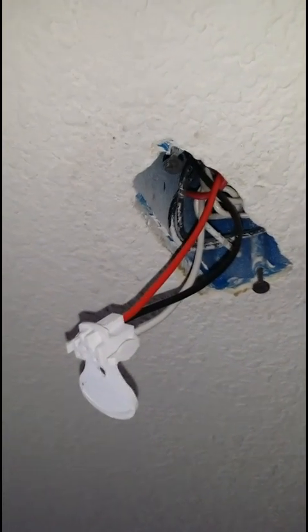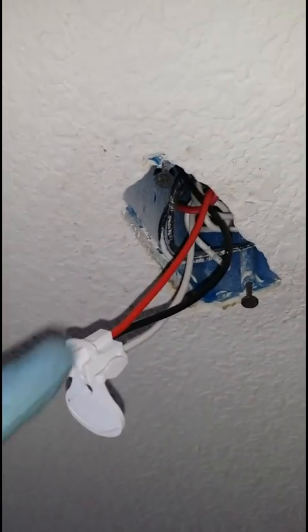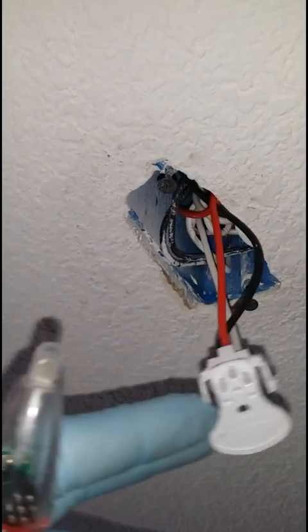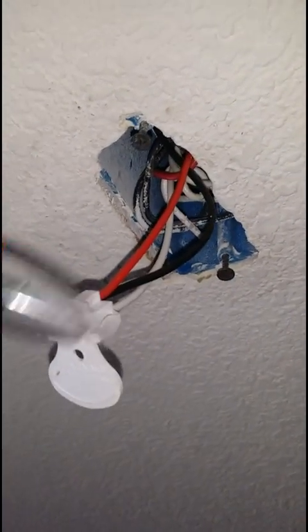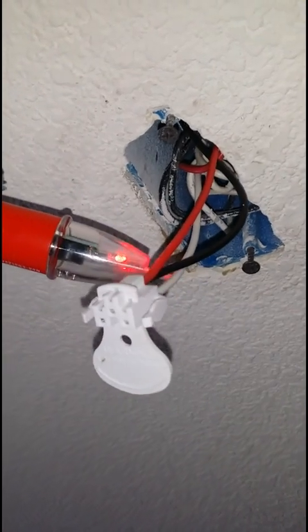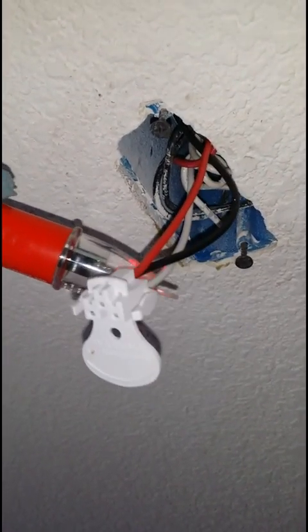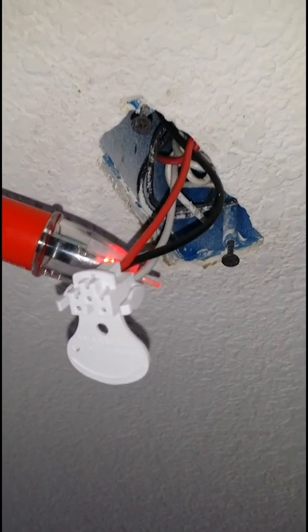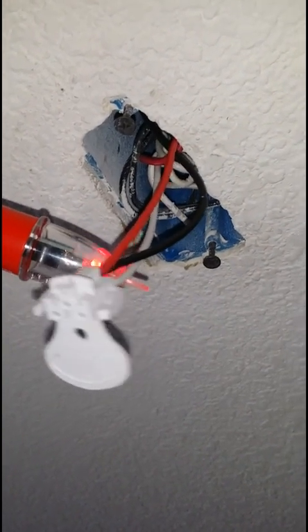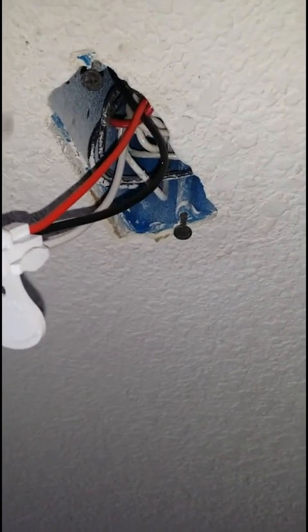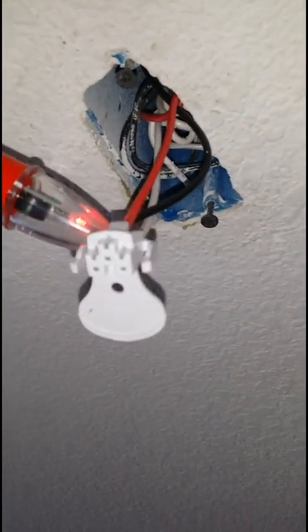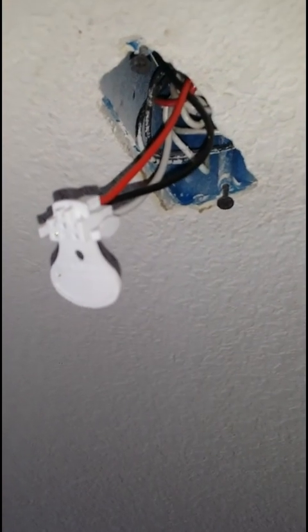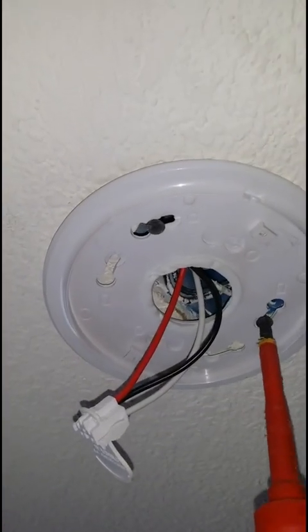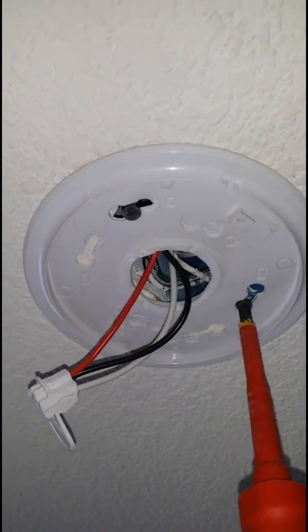Now what you'll want to do is push your voltage lines up, and you'll just want to leave the harness here. And like I said, you can test for power just to make sure that you didn't loosen any wires. If you're not comfortable, you can always disconnect the circuit breaker, turn it off, and then push the wires in and then turn it back on. Really depends on what you want to do. But right now we did push the leads up, and you can see here that we do have power going to the harness. Tighten down the screws for your base.